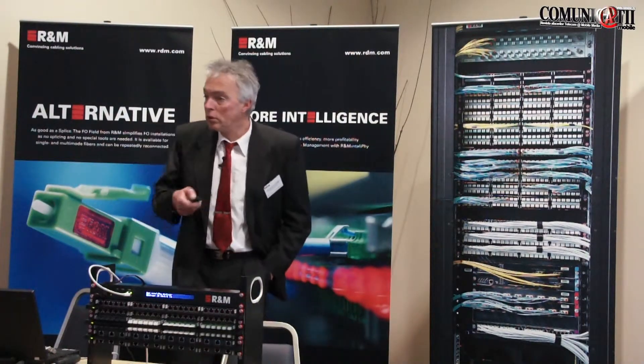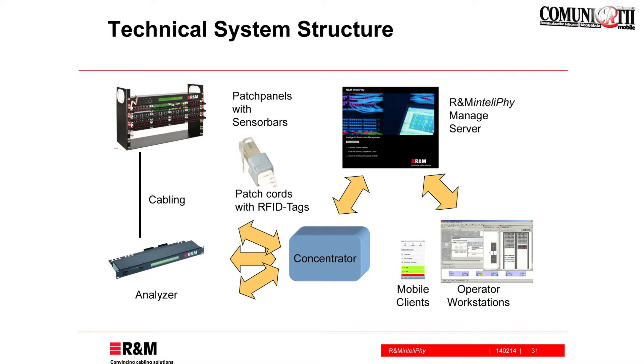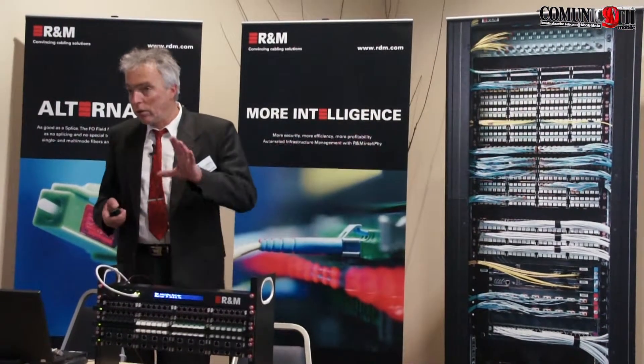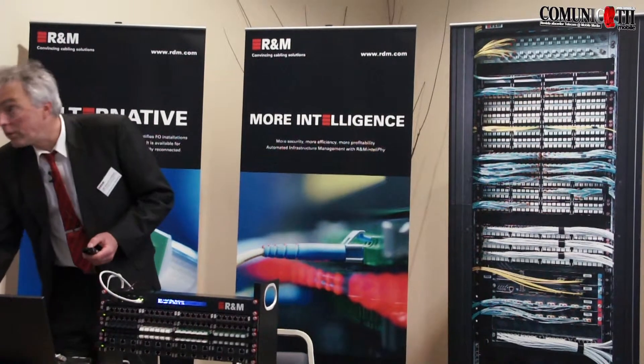Here is the complete system view — we have covered all of the components. Patch panels fitted with sensor bars, the cabling running to the analyzer. You can have many analyzers in an installation, typically one for every one, two, or three cabinets. There is a concentrator function — basically a PC which connects to all of the analyzers and has one single combined link to the server, informing the server about any changes in the network. Then we have graphical clients: a full-featured client for PC or Macintosh on reasonably large screens, and a small mobile client optimized for use on smartphones or tablets.